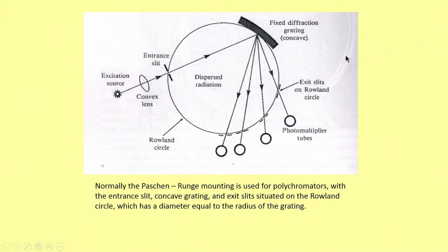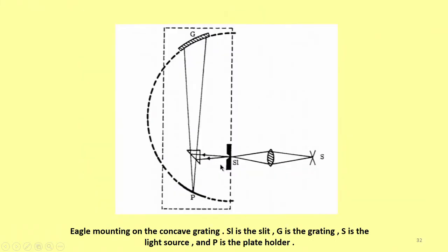You cannot fix sodium or potassium and then try to determine aluminum. You will not get it. You will be restricted to the wavelengths which have been factory fixed, depending upon the slit and detector arrangement.